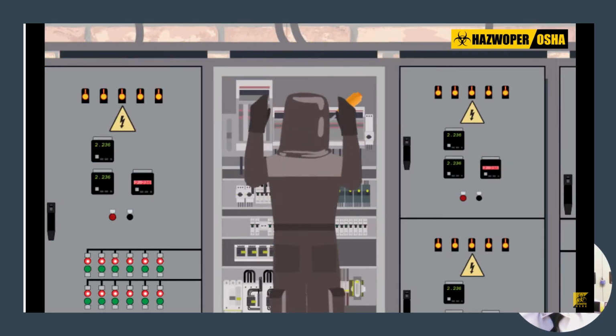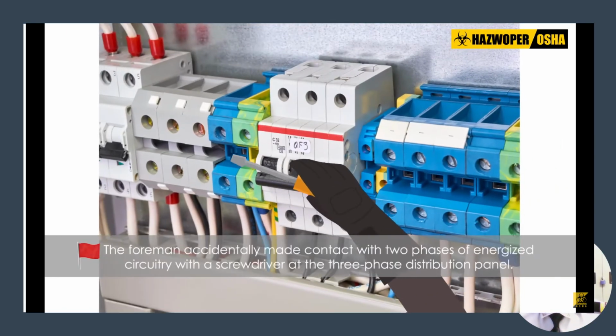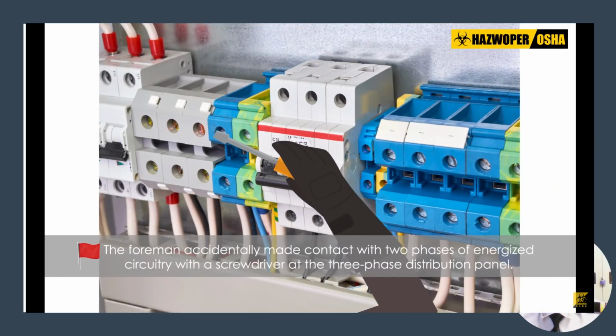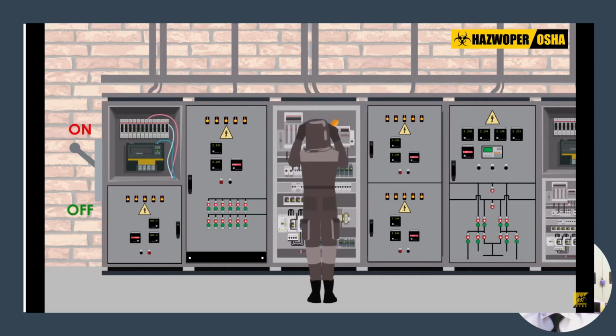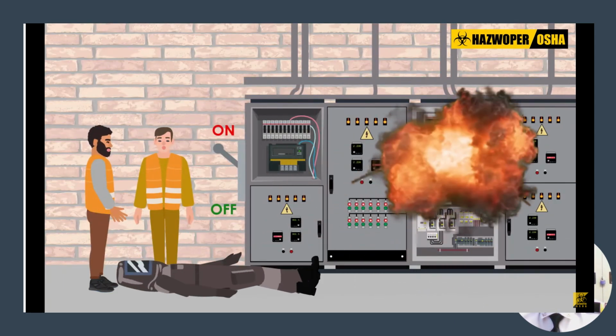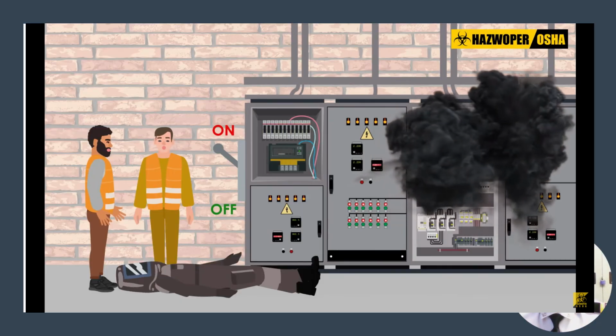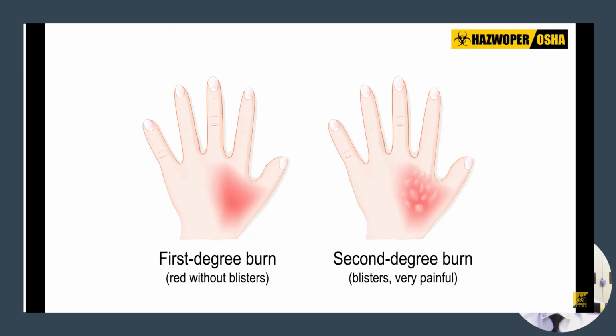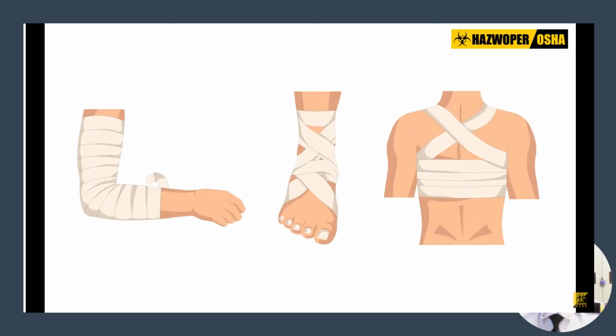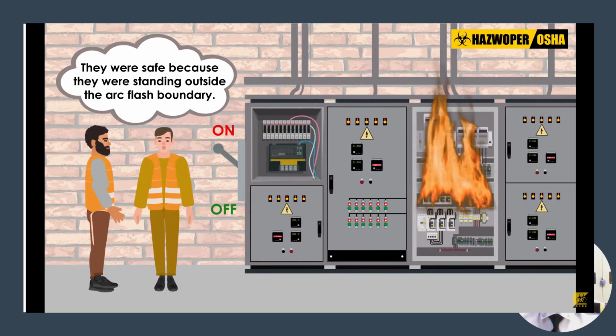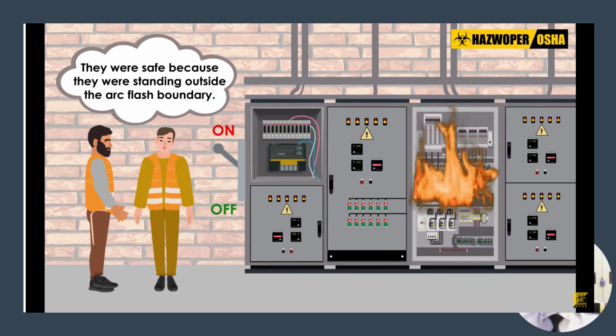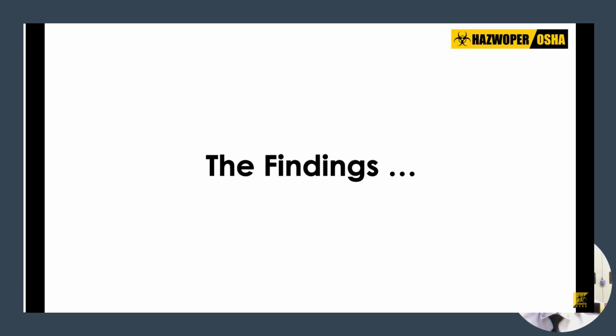As the foreman moved to the second circuit breaker, he accidentally made contact with 2 phases of energized circuitry with a screwdriver at the 3-phase distribution panel. This resulted in a blinding arc flash, followed by an explosion. The foreman was thrown backwards from the distribution panel due to the force of the explosion. He suffered first and second-degree burns on his arms, legs, and back. The other 2 foremen who were standing outside the arc flash boundary apparently suffered no injuries.